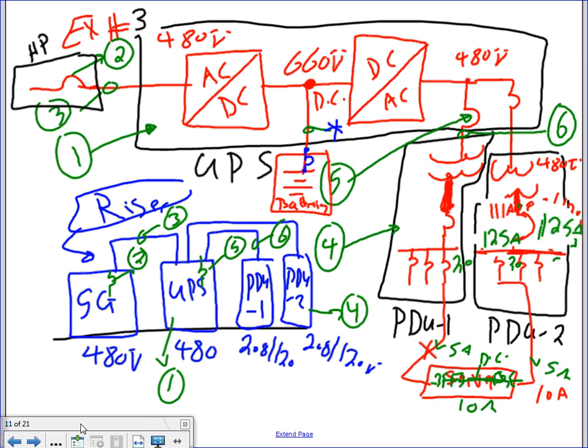Batteries, guys, work exactly like a battery. You take a 12 volt and a 12 volt, put them in series. What do you get? 24 volt. So you keep adding 12 volts until you build up enough voltage to get you close to 600 volt. And then they tie them to the DC bus. And then they bring them, that's inside the switch here. Then they bring them into a DC-AC inverter. Then they invert them back into AC. Now we're going back into the AC system.